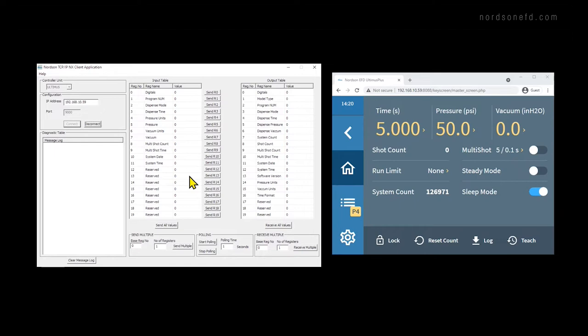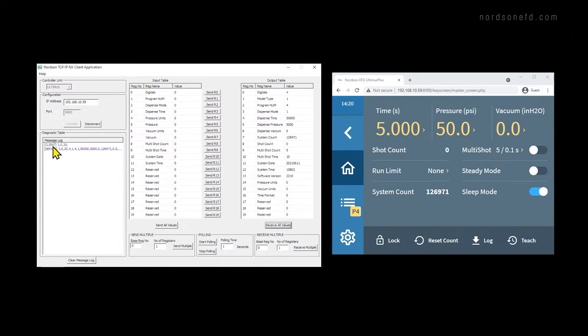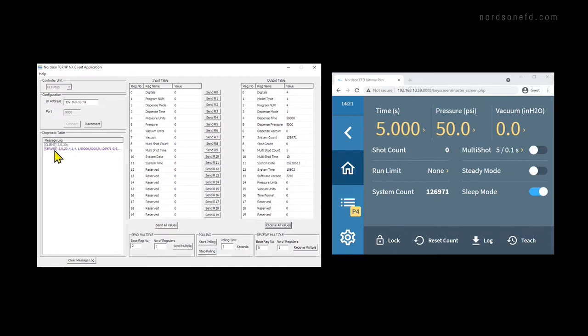The first thing I like to do to test our connection is to click receive all values, which will receive all of the values for each register from the unit. So you can see we have a digital value of 4 now in the output table. The diagnostic table shows what happened behind the scenes where we have our message log. So our client sent a message that was 3, 0, 20. What that means is the 3 corresponds to a read command. So we're going to be receiving or reading the values from the controller. The 0 indicates that we're going to be reading starting from register 0. And the 20 indicates that we're going to be reading 20 registers. So that means that we received from register number 0 all the way through register 19, or all the values. Then you can see the server responded with repeating our command, the 3, 0, 20, followed by all of the values in the output table.